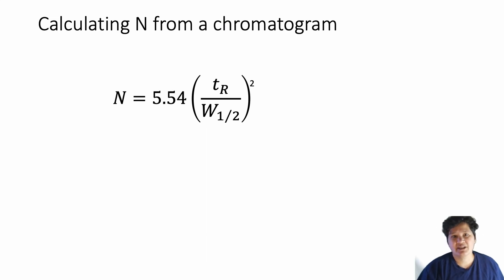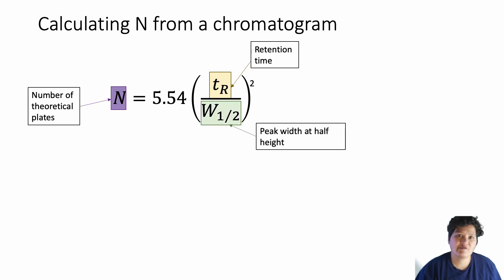We're going to calculate this based on measurements from our chromatogram, the output from our detector. So first, let's look at the equation. N is the number of theoretical plates in our column, which is equal to 5.54 times the retention time divided by peak width at half height, that quantity squared. People are often confused by what peak width at half height means. So let's go into that in a little more detail.